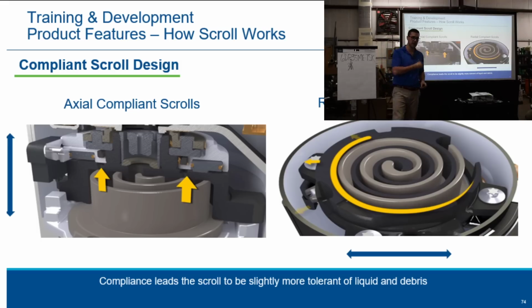I've got a video that I'm going to show you in a minute that's going to say liquid tolerant. Okay, it's a little bit of scroll, liquid can go in it. But what does that liquid do inside that scroll? What's inside the scroll set while it's running at all times? Oil, right? So right here, between this fixed and this orbiting scroll, you've got an oil film in there to keep that seal while it's pumping. So now tell me what happens. What's refrigerant? It's a good what? Solvent.